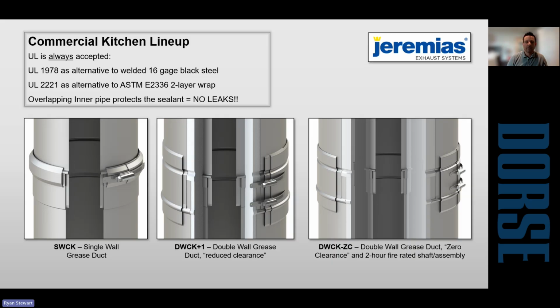So it has 2 layers of wrap, and then you've got to maintain between 1 and 3 inches of clearance to the outside, just depending on diameter. And then they offer a true zero clearance, which just has more insulation. For the most part, I see people using the reduced clearance. In most cases, you can get the couple inches that you need to the outside of the ductwork.